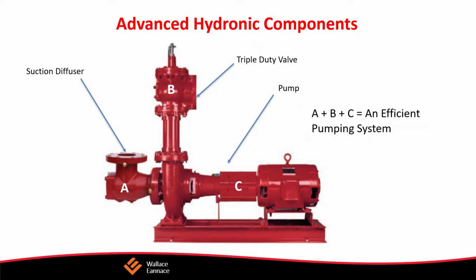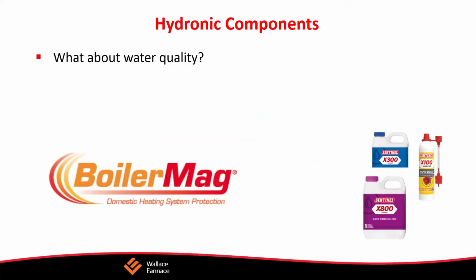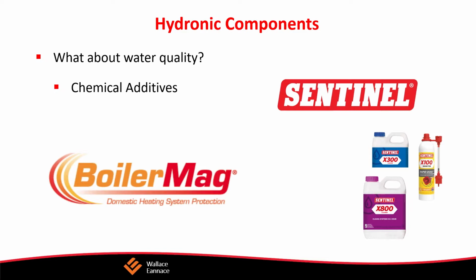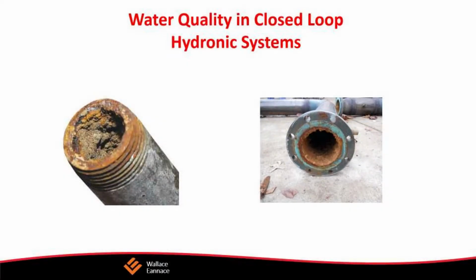Here we have a device, the triple duty valve, which is placed on the discharge side of the pump. It combines 3 functions into one device. This is why it's called a triple duty valve. It's a calibrated balancing valve. You can see here's the gauge here. It's a spring-loaded check valve, and it's an isolation shutoff valve. So this device serves 3 functions in one device.